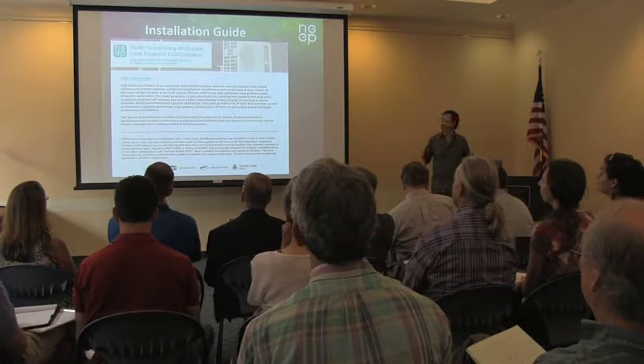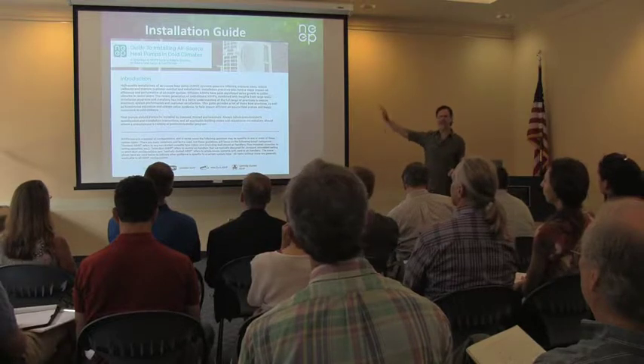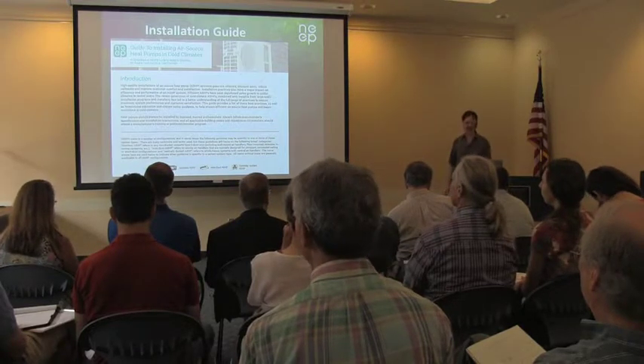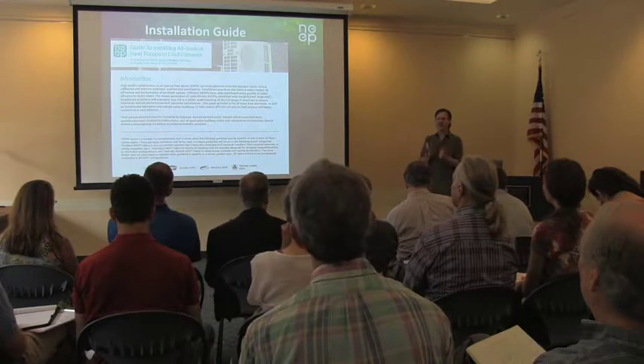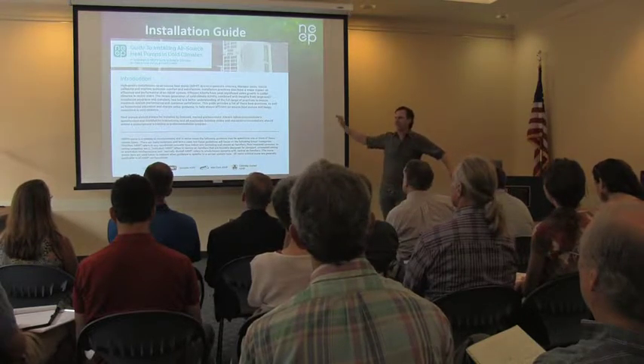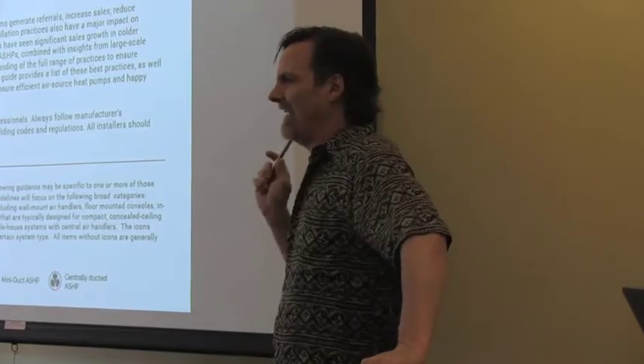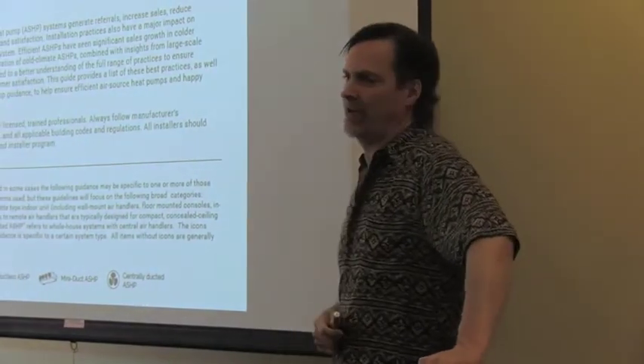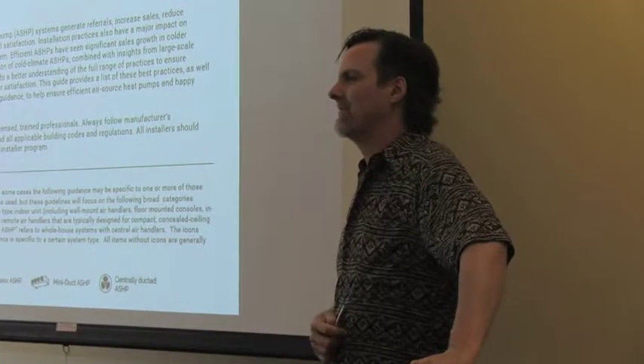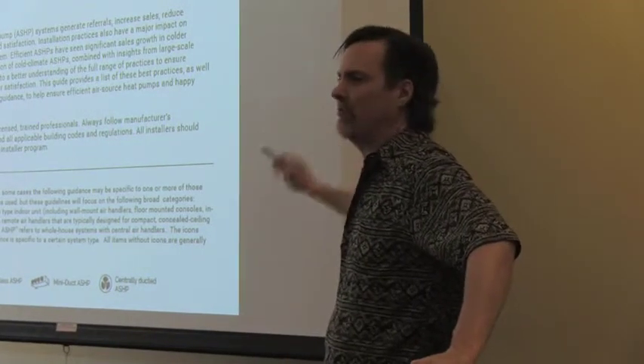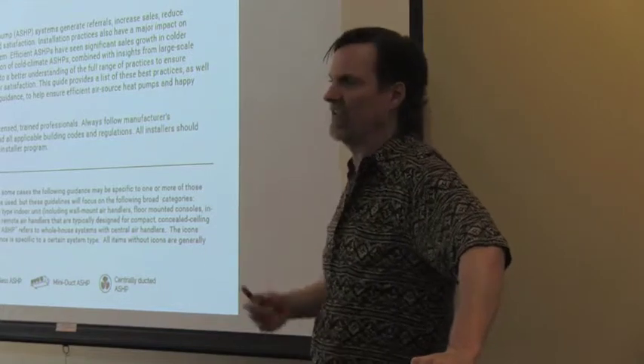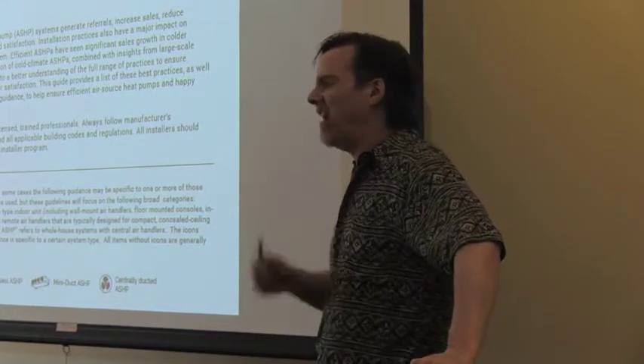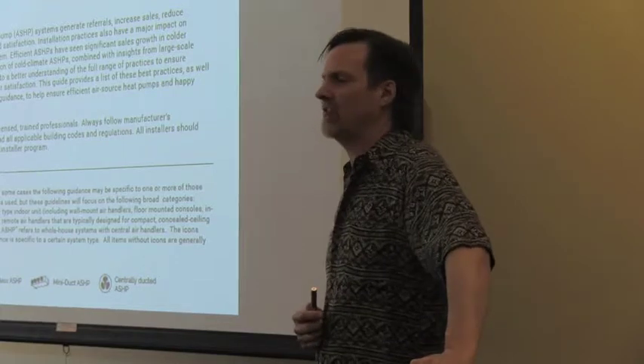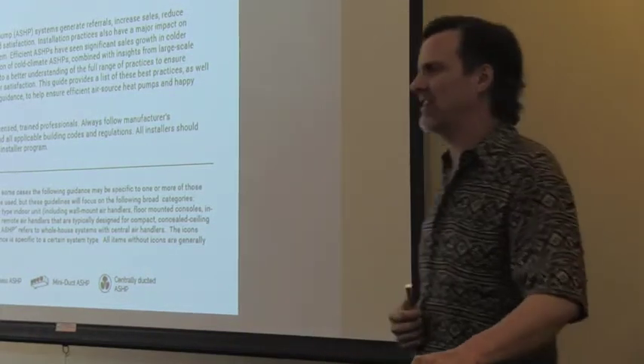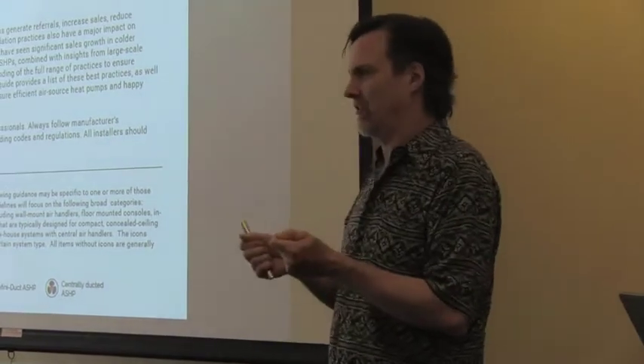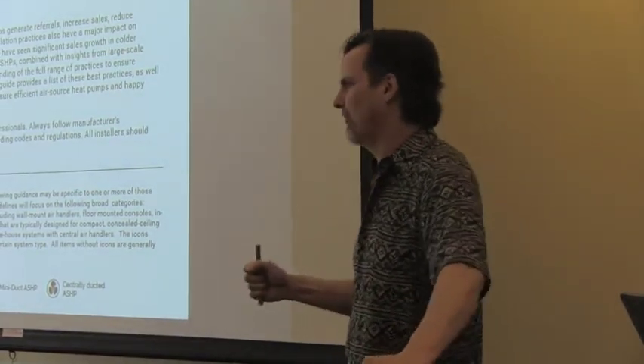And then the installation guide: there's some introductory material, and then essentially there's a checklist format with a lot of information. Most of the items in this installation guide, if you actually look closely, are exactly the same as manufacturers' recommendations for how to do an installation. So what we're proposing that people do isn't really any different than what the industry is saying, this is how you should install these units. But not all installers pay attention to those manufacturers' instructions. I think it's kind of a guy thing, like nobody wants to be seen reading the directions. We're supposed to know how it works.